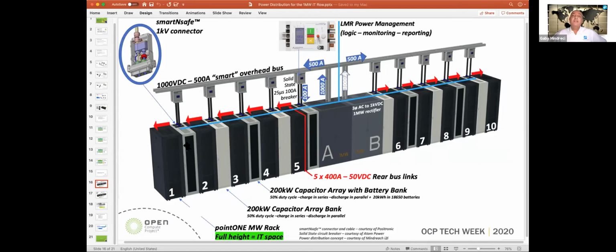Should anything need to be changed, it would require disconnection of the branch that needs to be changed, and it would require shorting of all capacitors as a safety element in order to access and physically service the units. Obviously, new training, new methodology and procedures would have to be written accordingly.